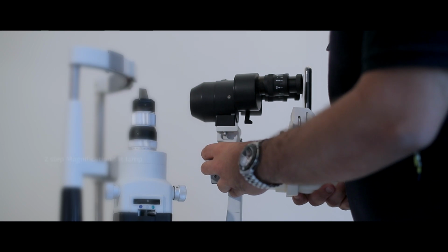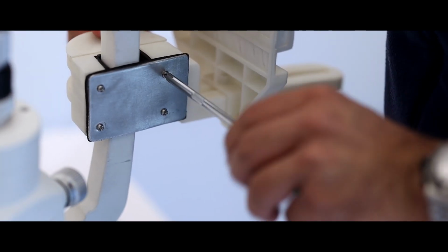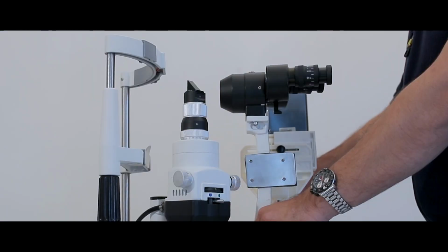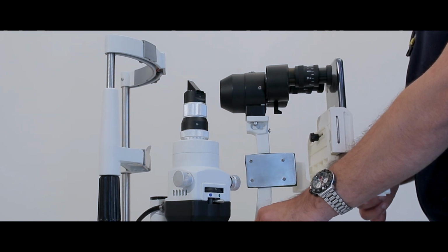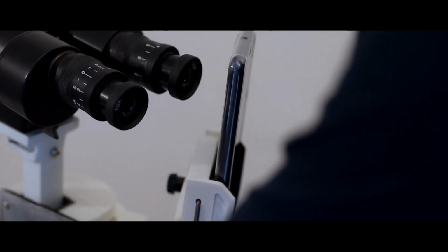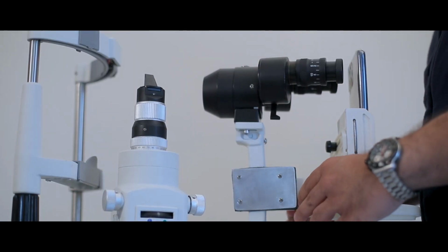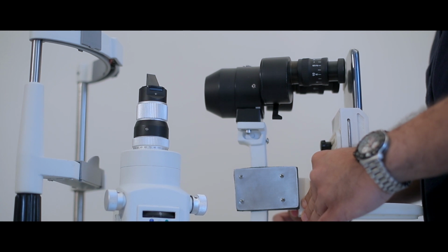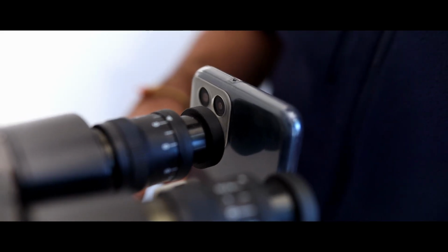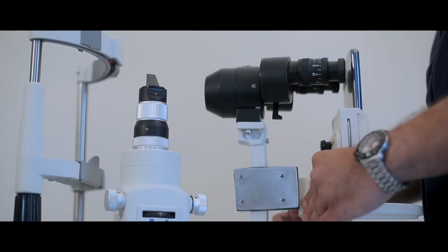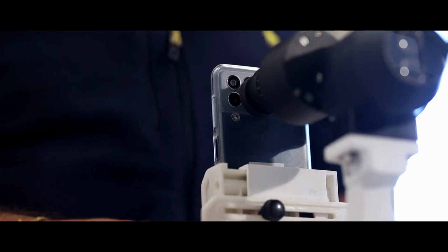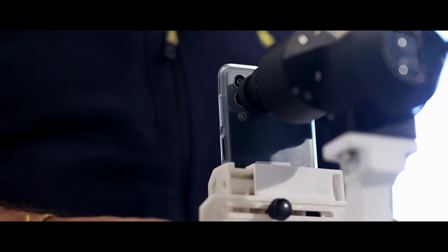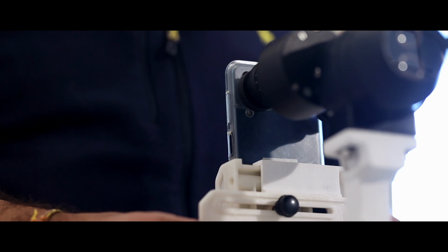The device has a unique design that enables it to be mounted on the handle of the slit lamp and can be rotated in and out of the eyepiece for capturing eye images very easily. Place the mounting block onto the slit lamp handle in a way that the smartphone camera is in line with the right eyepiece of the slit lamp. The distance between the smartphone camera and the eyepiece is typically 3 to 5 millimeters.